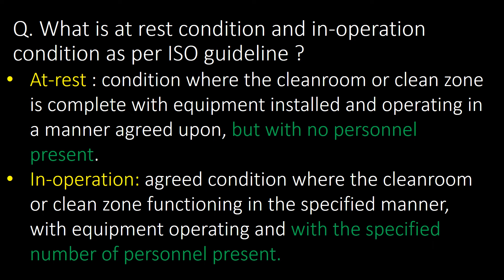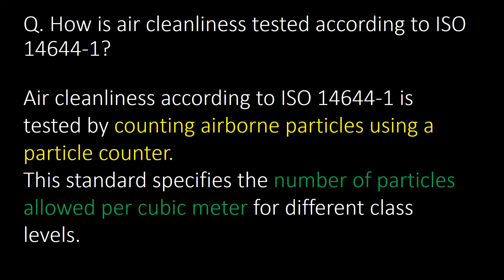The fundamental difference between these two conditions is the presence of personnel. How is air cleanliness tested according to ISO 14644-1? Air cleanliness according to ISO 14644-1 is tested by counting airborne particles using a particle counter. This standard specifies the number of particles allowed per cubic meter for different class levels.